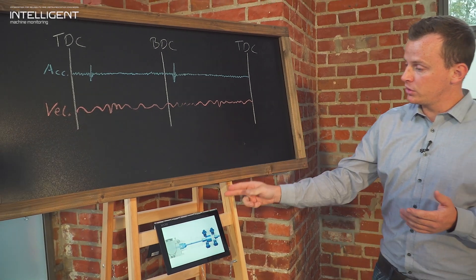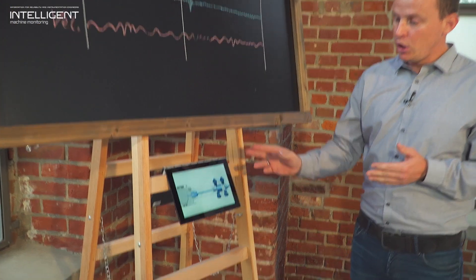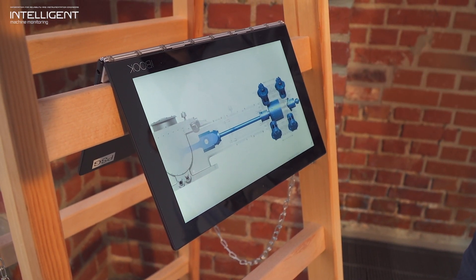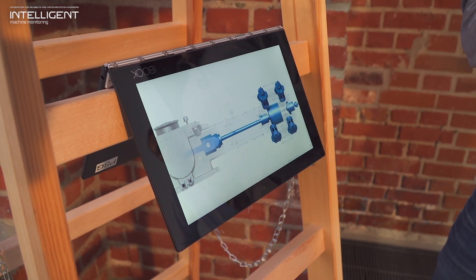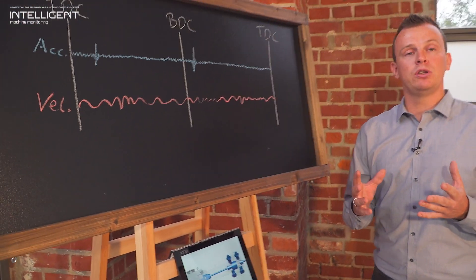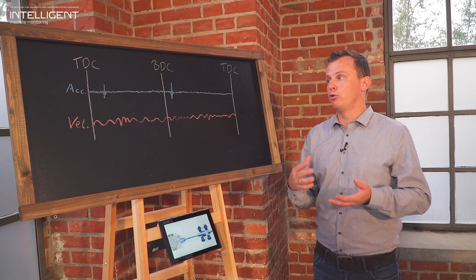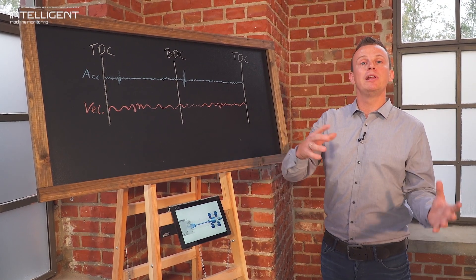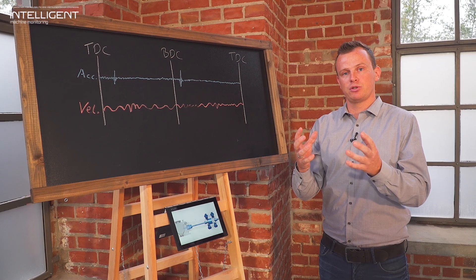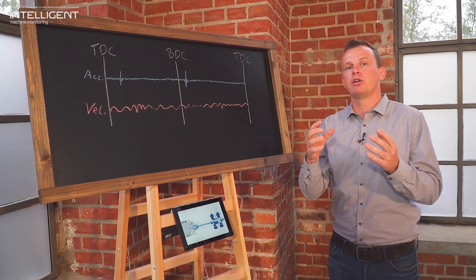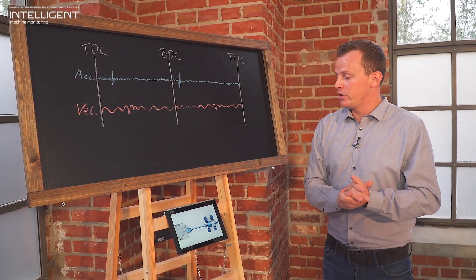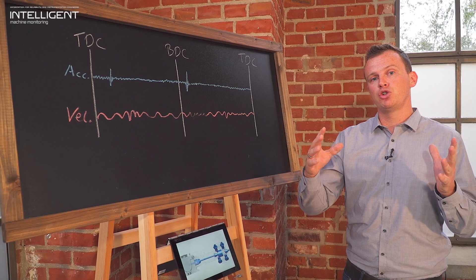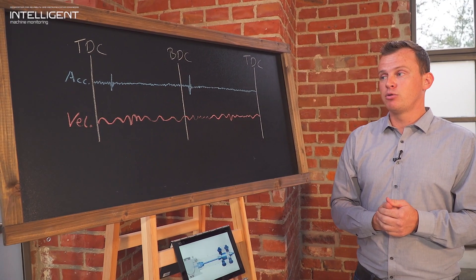The frame is a good reference point. Looking at the machine in this picture, we see an overview of one cylinder of the compressor. Frame vibration signals are mainly measured directly on the housing of the compressor, which is a good example for a frame vibration probe placement. On that part of the compressor, we do not see impacts from valve load reversal points. We see slow-moving vibrations caused by the complete machine. The complete machine cannot shake at high frequency, so we look at low frequencies to monitor that area. This is also a protection probe — we build up the RMS value over one revolution and can trip the compressor based on that signal.